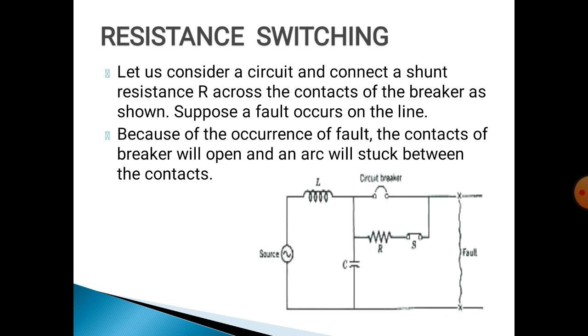In this circuit, we have considered the circuit breaker to be an air blast circuit breaker or oil circuit breaker. If a fault occurs in a particular line, the circuit breaker senses the fault current and voltage. At that time, the circuit breaker switch will open. When the switch opens, an arc is produced between the circuit breaker contacts. The resistance reduces the arc. So in this method of resistance switching, the resistance is connected in parallel with the contact space, that means the contact arc, to overcome the effect of transient recovery voltage.